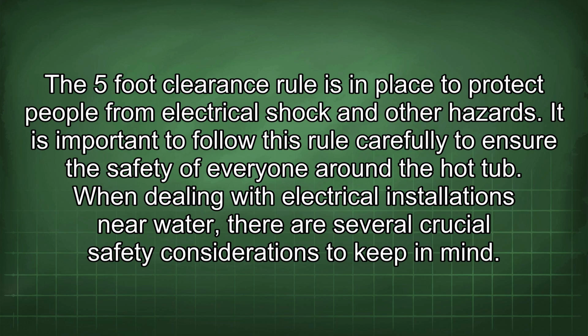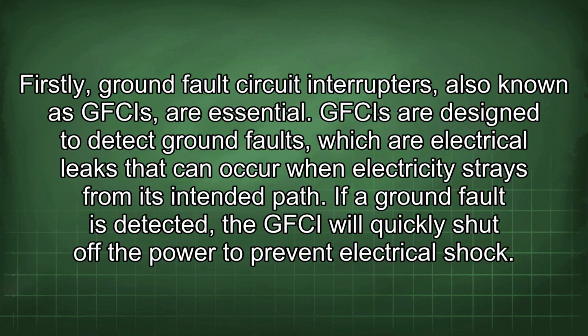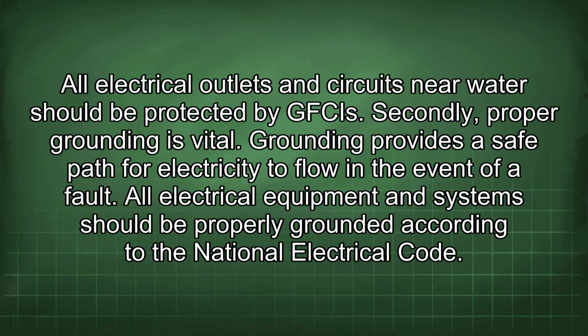When dealing with electrical installations near water, there are several crucial safety considerations to keep in mind. Firstly, ground fault circuit interrupters, also known as GFCIs, are essential. GFCIs are designed to detect ground faults, which are electrical leaks that can occur when electricity strays from its intended path. If a ground fault is detected, the GFCI will quickly shut off the power to prevent electrical shock. All electrical outlets and circuits near water should be protected by GFCIs.